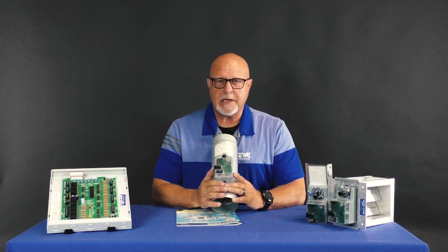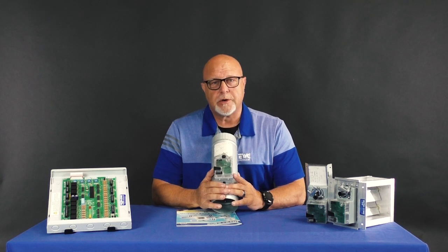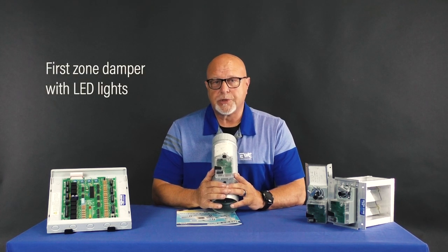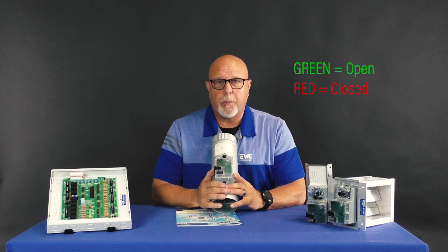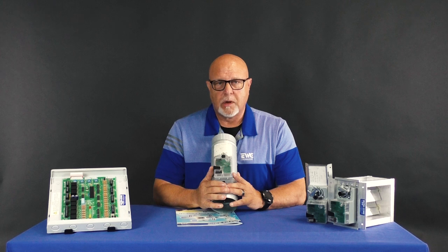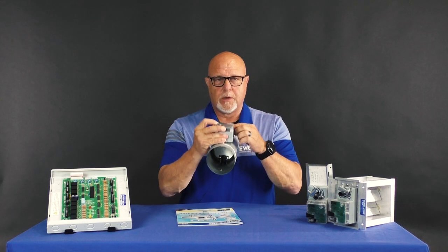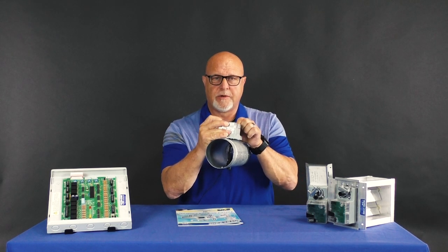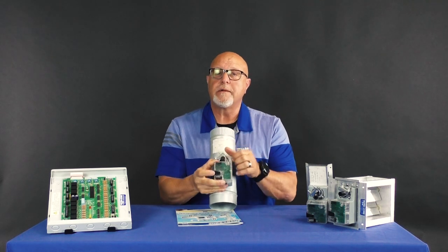One of the very nice features about EWC is that in 2004 we introduced the first zone damper with LED lights. These are true position indicator lights. If it's green, it is open. If it is red, it is closed. And you can see these lights anywhere between 70 and 80 feet, depending on how dark the space is that you have placed our damper. This LED light will only be off in 2 scenarios. It is moving in that 35-second transition from open to close or vice versa, or there is something wrong.